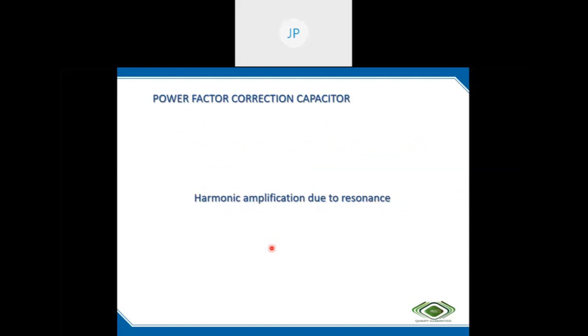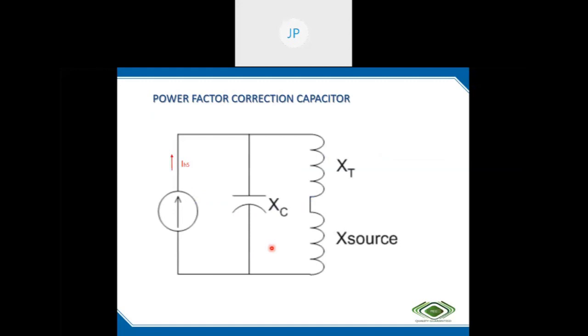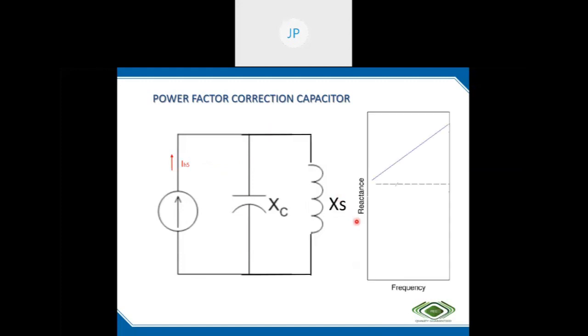So the next issue is harmonic amplification due to resonance. Again, we are considering the simplified diagram. First, we are considering amplification of voltage. For that, we always need to first calculate the equivalent impedance, so we are reducing this circuit. By this time, you can see this is the frequency versus reactance curve of impedance Xc.